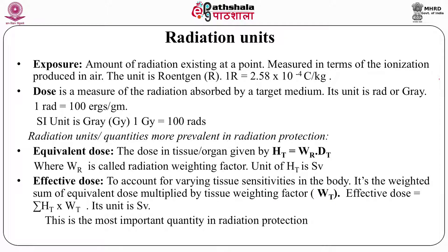Before progressing on radiation protection, let's look at radiation units. The first quantity is called exposure — the amount of radiation existing at a point, measured by the ionization produced in air. Its unit was the Roentgen, named after the discoverer of X-rays. One Roentgen was defined as one electrostatic unit of charge collected per cc of air at normal temperature and pressure. In SI units, one Roentgen equals 2.58 × 10⁻⁴ coulombs per kilogram of charge collected.